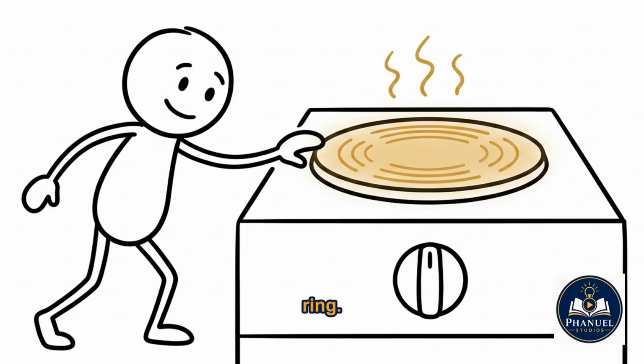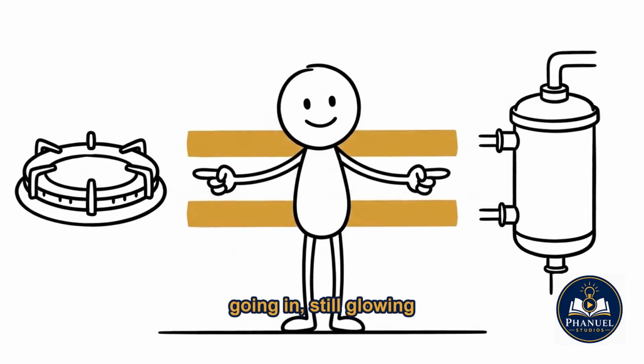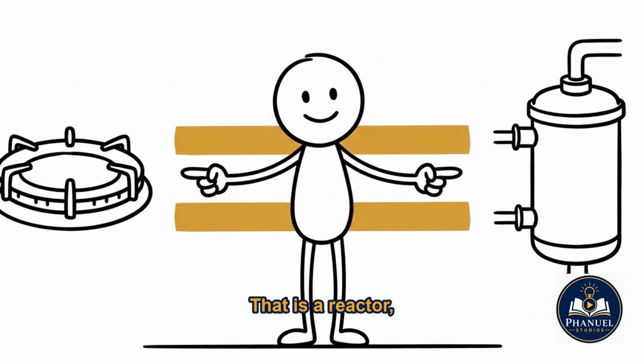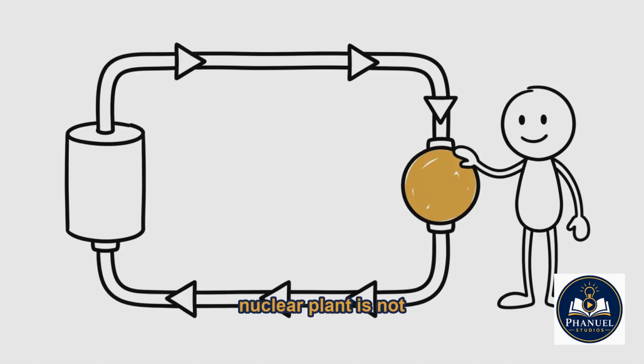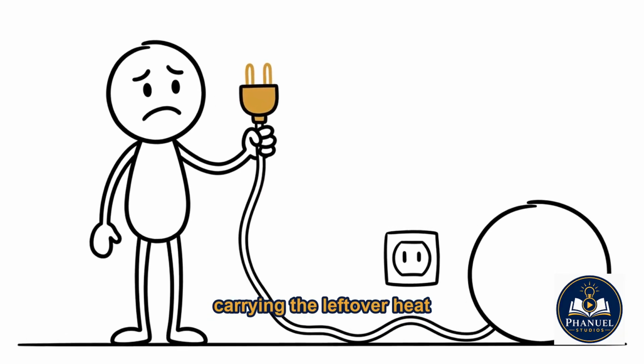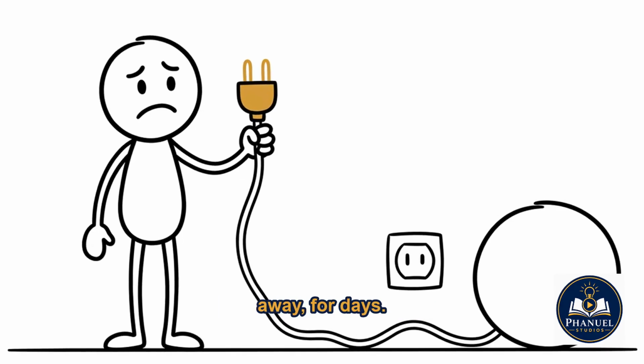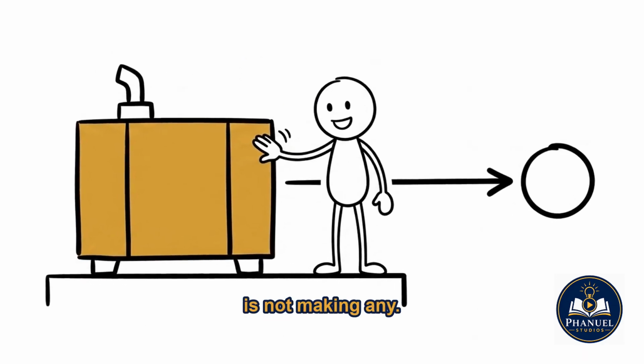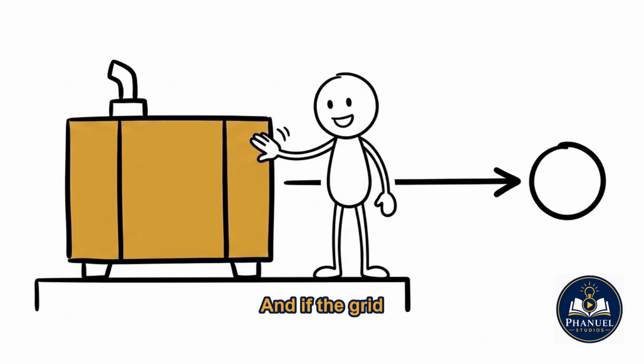Picture an electric stove ring. Knob at 0, nothing going in, still glowing orange. That is a reactor, except the ring is worth 200 megawatts, and it takes years to stop glowing. Which means the most important machine at a nuclear plant is not the reactor. It is the pumps. Water has to keep moving through that core, carrying the leftover heat away for days. Pumps need electricity, and the plant has just tripped, so it is not making any. It runs on the grid, and if the grid is gone, on diesel generators.